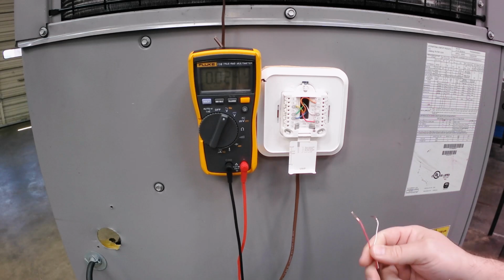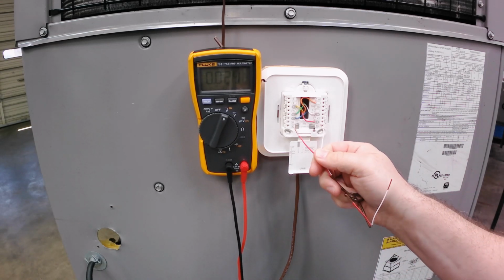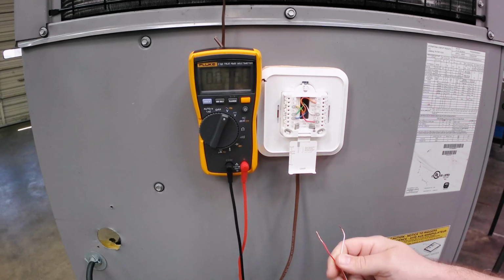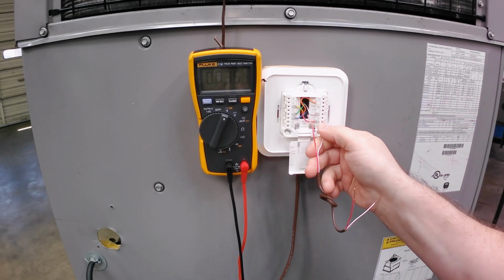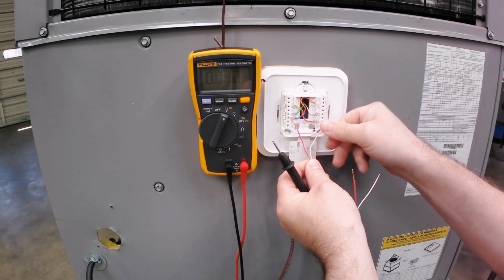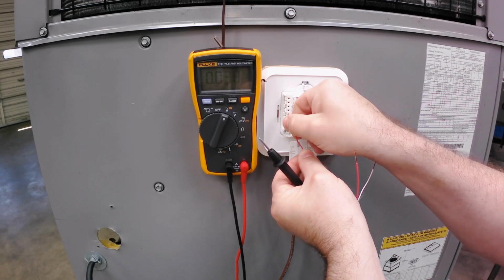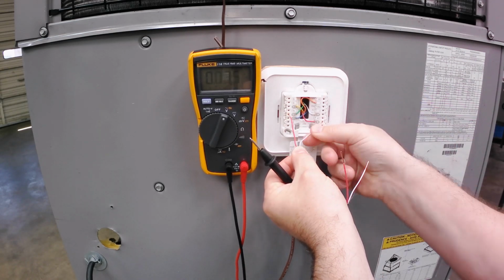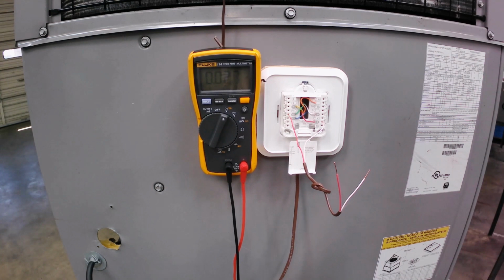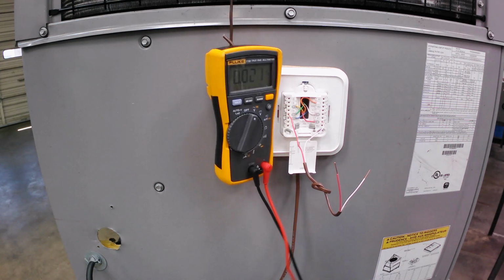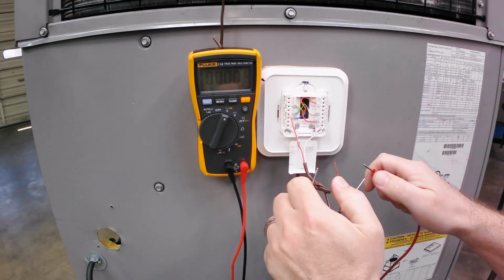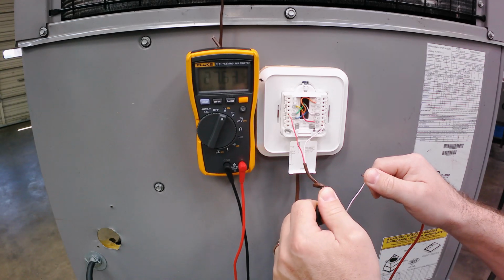So when you're checking voltage, I'll go through and show you here. You just saw me check R and C, I got 24 volts. If I were to leave that one wire in that pin and check to G, R to G, if I do the same voltage check on this thermostat, guess what I'm going to get? 27 volts. And you're like, oh, I got power.